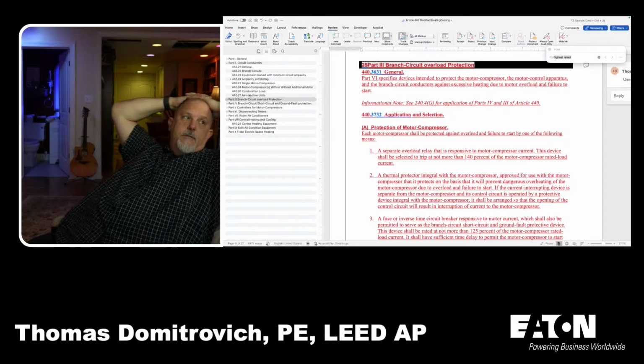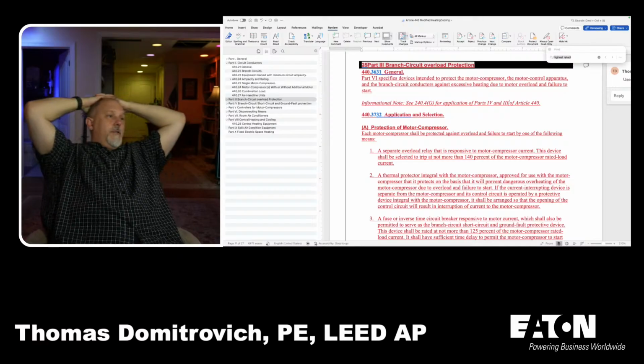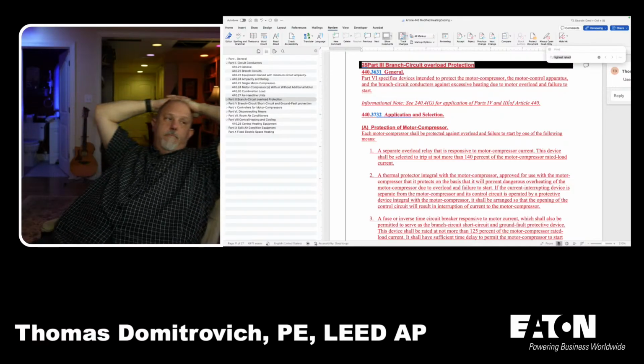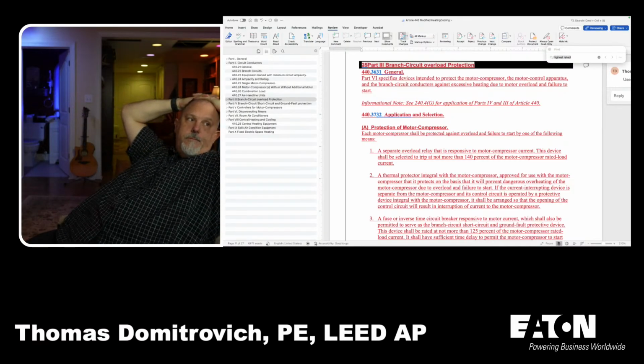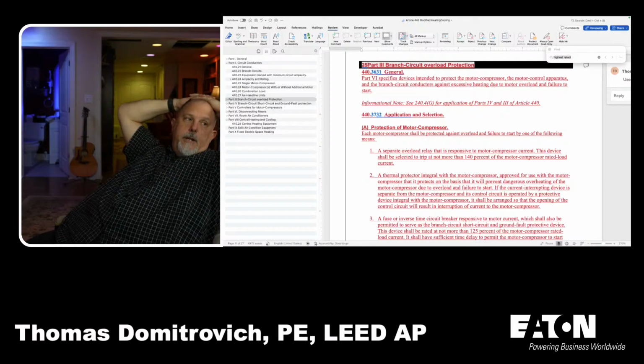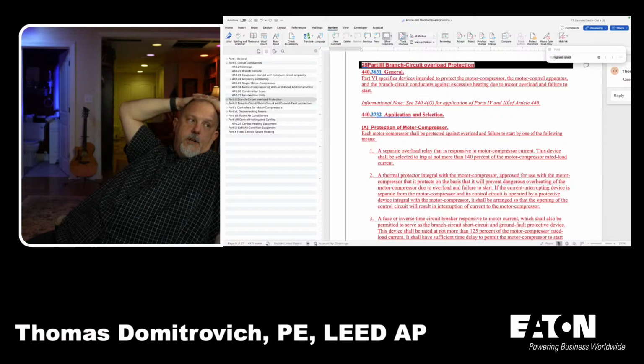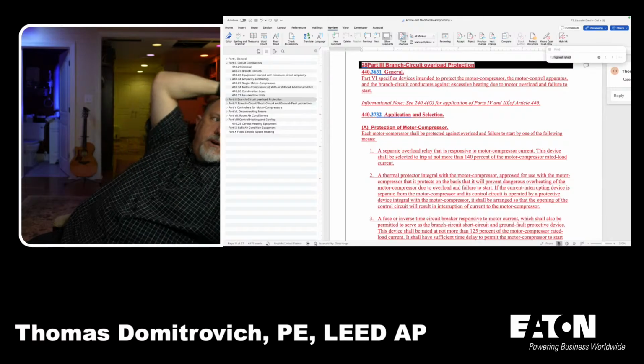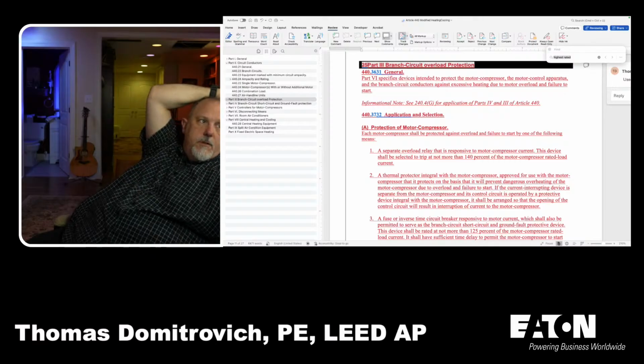I can't have an informational note that references the part that I'm already in. Application and selection. Protection of motor compressor. Each motor compressor shall be protected against overload and failure to start. So these are all overloads.